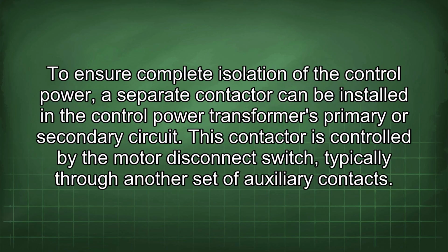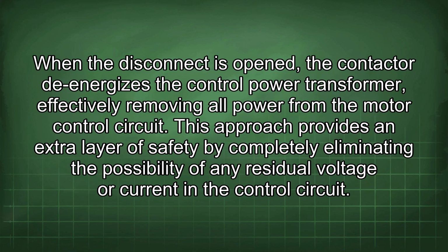To ensure complete isolation of the control power, a separate contactor can be installed in the control power transformer's primary or secondary circuit. This contactor is controlled by the motor disconnect switch, typically through another set of auxiliary contacts. When the disconnect is opened, the contactor de-energizes the control power transformer, effectively removing all power from the motor control circuit. This approach provides an extra layer of safety by completely eliminating the possibility of any residual voltage or current in the control circuit.